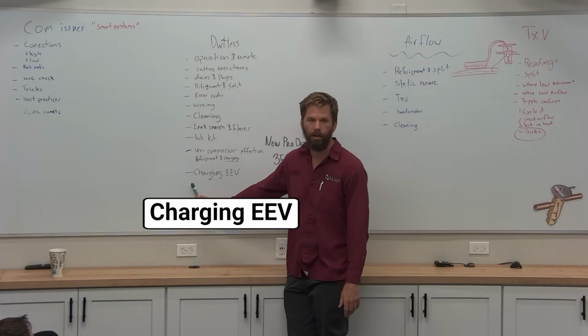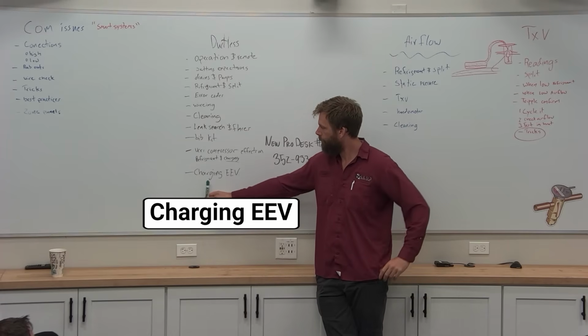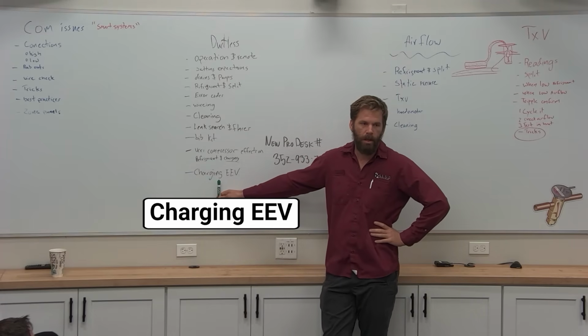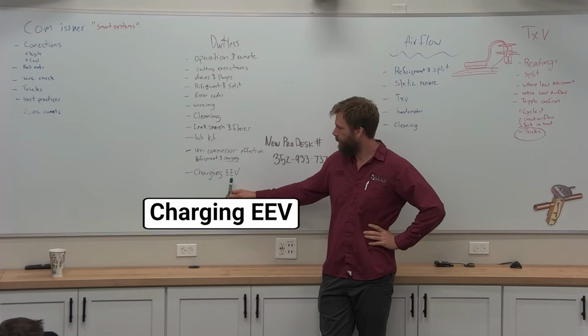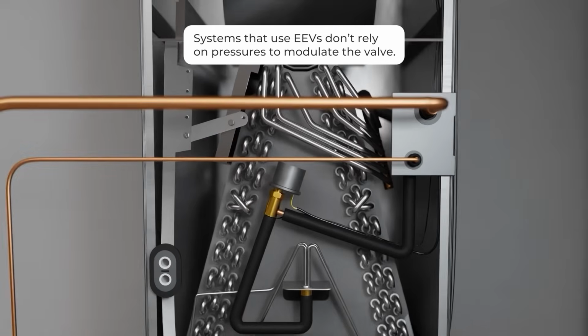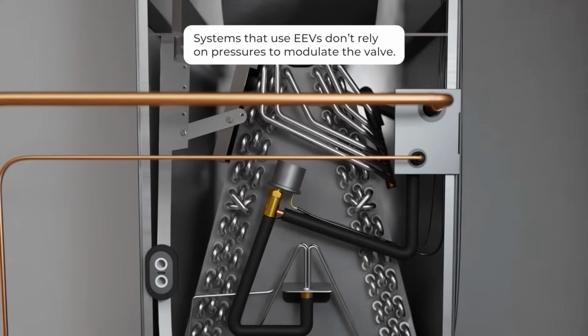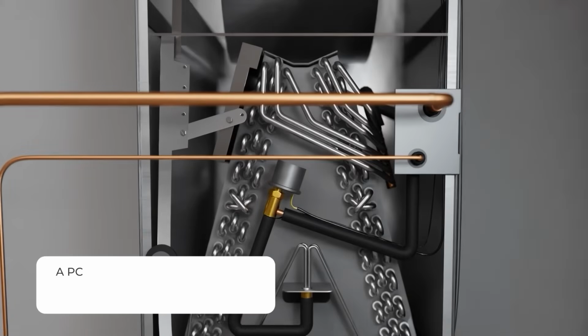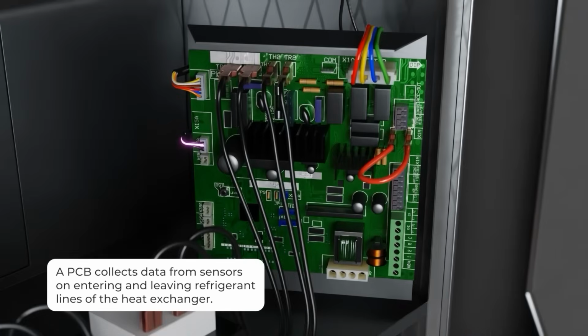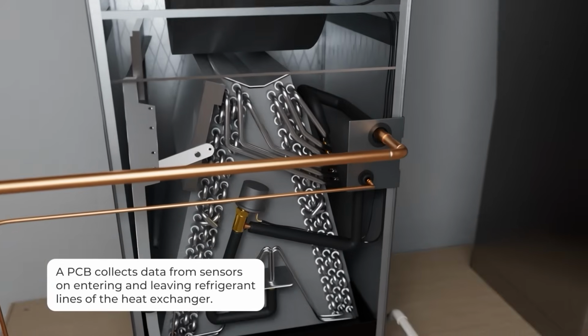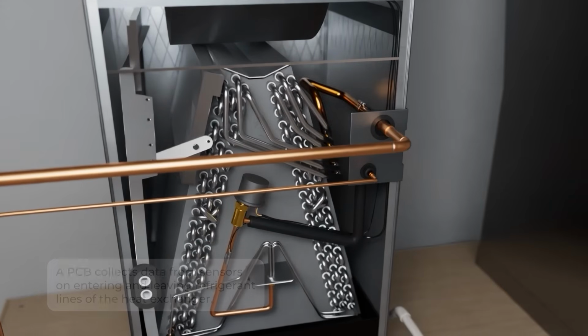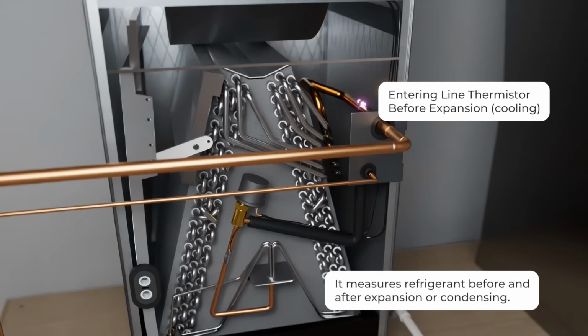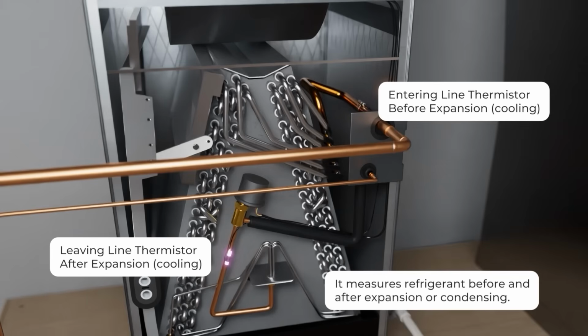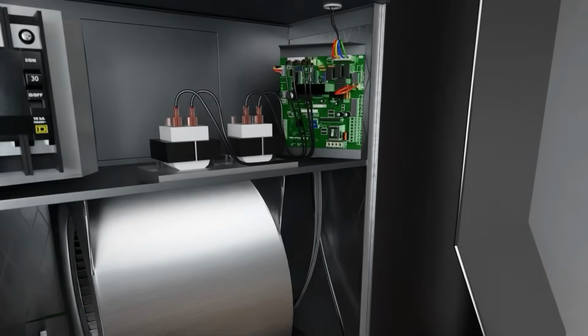When you are charging, you go to add refrigerant to a system. The thing that makes it tricky is that it's an electronic TXV. The electronic TXV measures the line temperature electronically on the suction and then electronically adjusts based on what it's measuring. If you add refrigerant, you change the temperature of the line. As the refrigerant rushes in, it creates a really cold line, which means your electronic TXV starts to adjust as soon as you start adding.